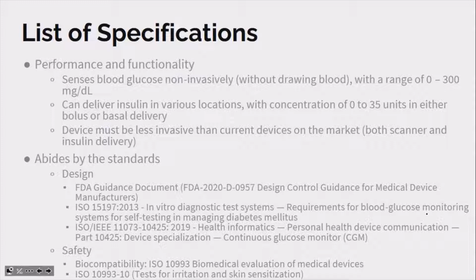The ISO 15197 talked about the accuracy standards that needed to be for a glucose meter at different concentrations. The ISO 11073 talked about how often the glucose monitor needed to detect values to be considered a continuous one. And then the ISO 10993 talked about the safety and biocompatibility the device needs to have with the body.